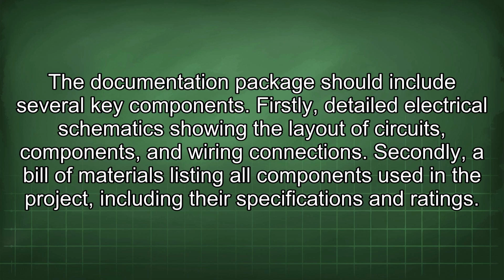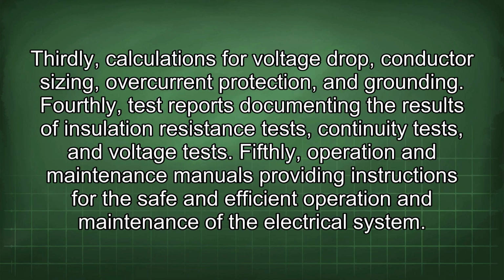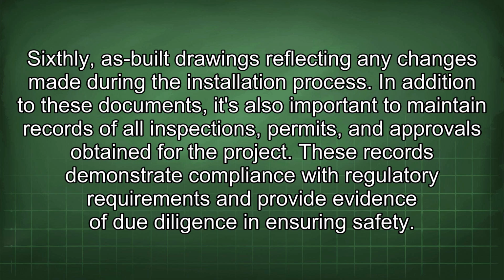Firstly, detailed electrical schematics showing the layout of circuits, components, and wiring connections. Secondly, a bill of materials listing all components used in the project, including their specifications and ratings. Thirdly, calculations for voltage drop, conductor sizing, overcurrent protection, and grounding. Fourthly, test reports documenting the results of insulation resistance tests, continuity tests, and voltage tests. Fifthly, operation and maintenance manuals providing instructions for the safe and efficient operation and maintenance of the electrical system. Sixthly, as-built drawings reflecting any changes made during the installation process.